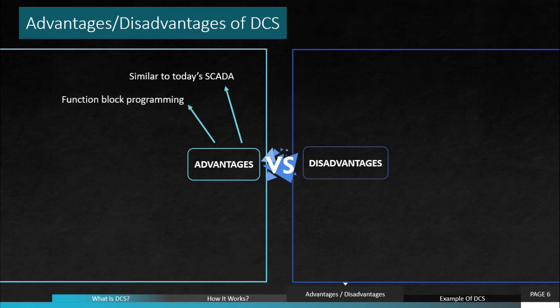Secondly, DCS has function block programming. Block programming is defined as several lines of code behind a single interface. The function of the interface is to handle the manual and automatic operation of a valve. Function block programming also saves a lot of time and redundant programming. Next, the advantage is on installation costs.